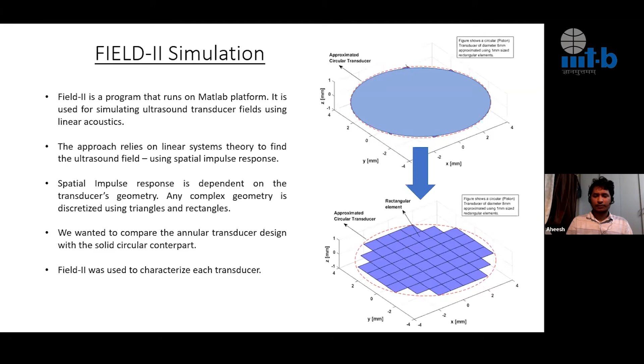So predominantly how the software works is we have to create a transducer surface and discretize it. Here, for example, I've shown a very bad discretization of a continuous circular transducer surface, just to show that it discretizes the surface, but we could discretize it using even smaller squares. So the algorithm runs for each particular square which has been discretized to mimic the circular nature of the transducer, if we are trying to calculate the ultrasound field for a circular transducer. So these were the two transducers which we tried, and this tool is very versatile. We realized that we could get 2D images and perform beamforming and all other advanced concepts which are already present in the industry.